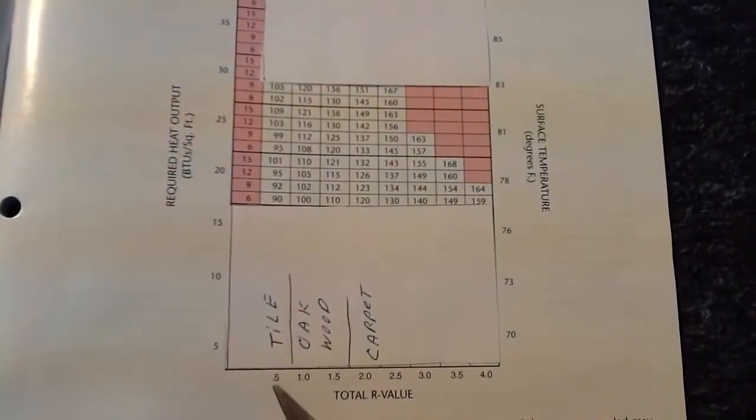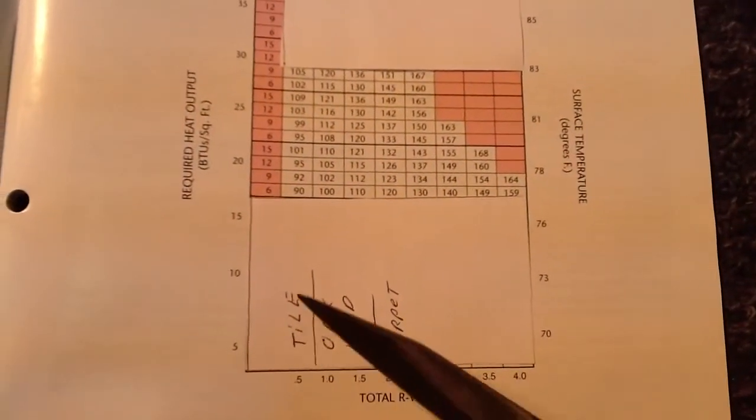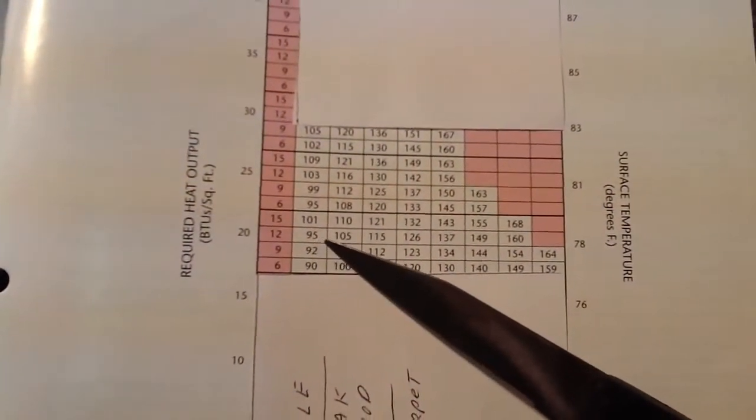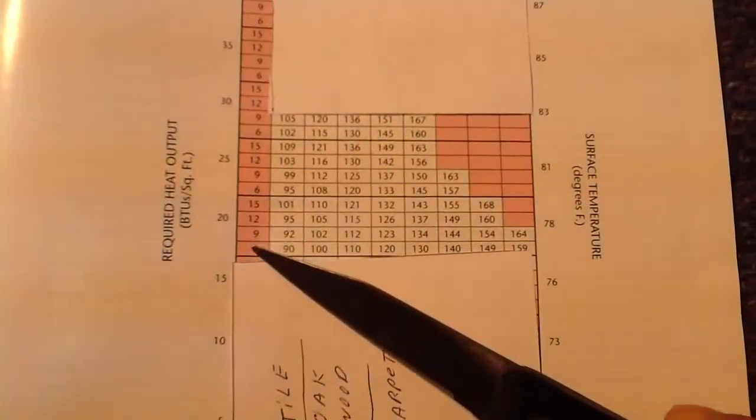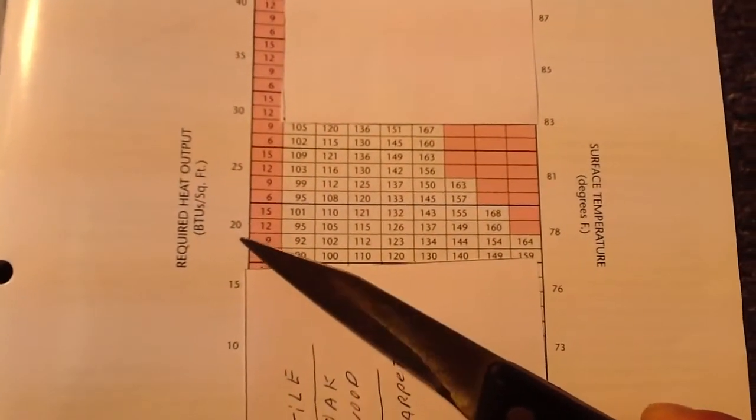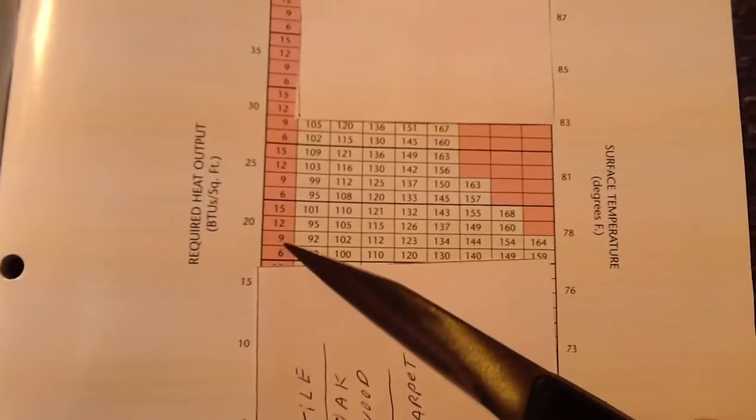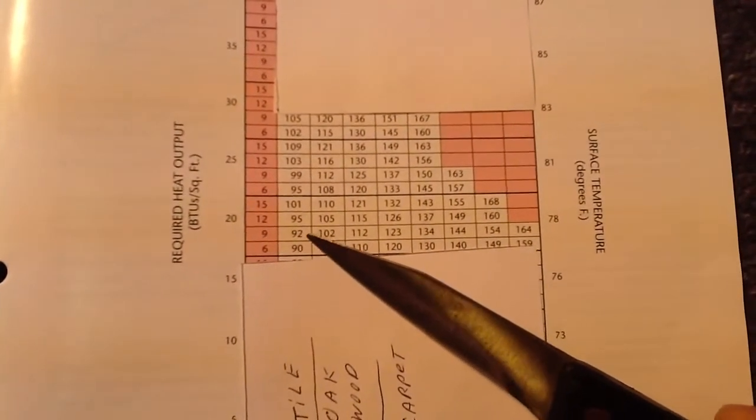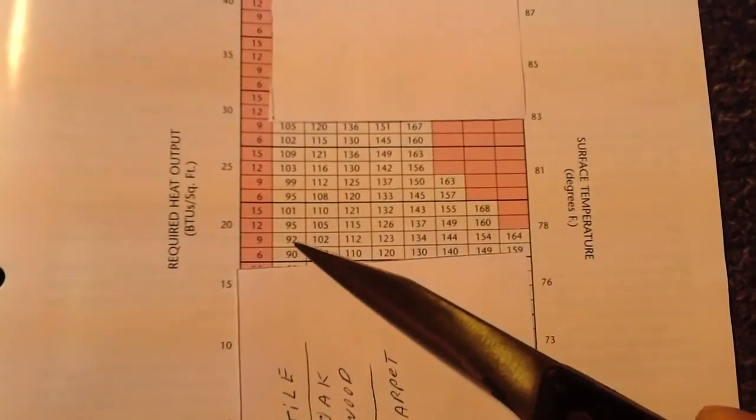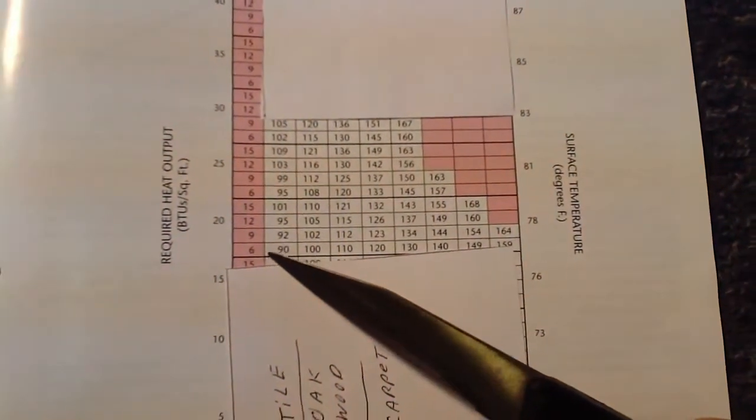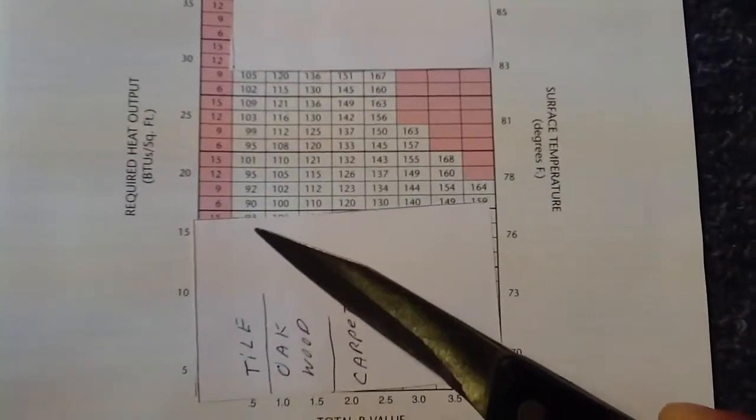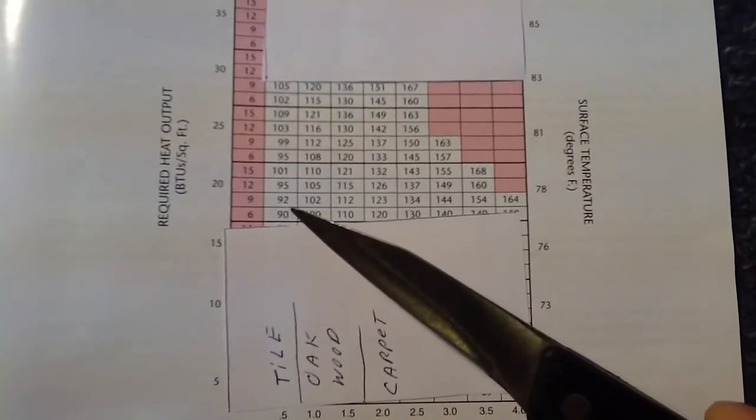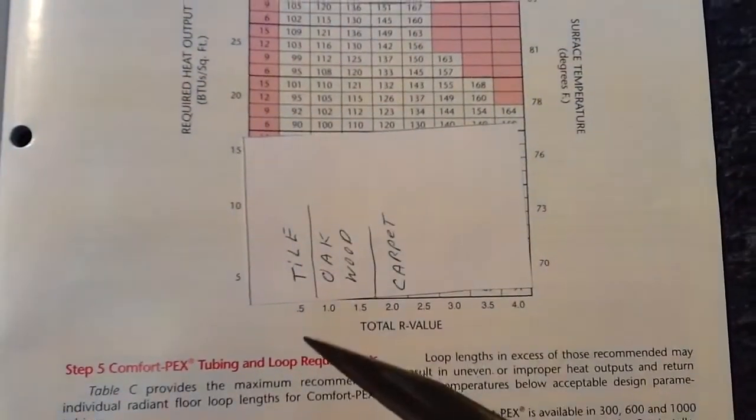So very easily, 0.5 tile, which is this line here, if you were to want to achieve 20 BTUs per square foot, if you have 9-inch spacing loops, you need 92-degree water. As you can see that, that's with tile.